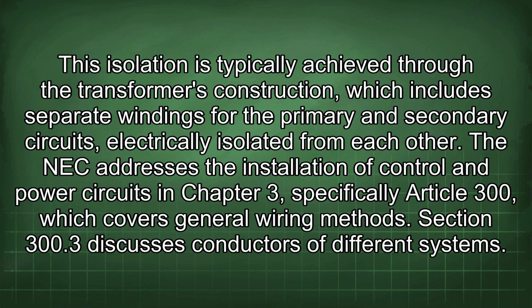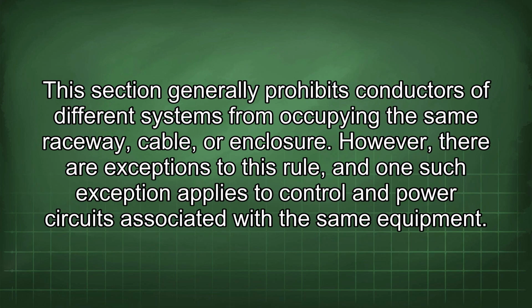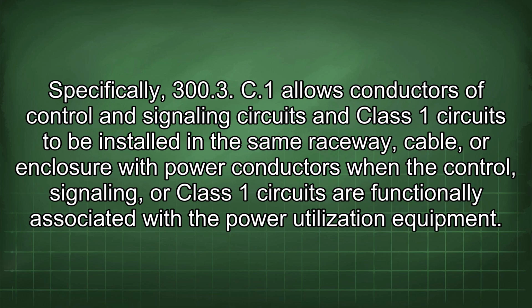Section 300.3 discusses conductors of different systems. This section generally prohibits conductors of different systems from occupying the same raceway, cable, or enclosure. However, there are exceptions to this rule, and one such exception applies to control and power circuits associated with the same equipment. Specifically, 300.3(C)(1) allows conductors of control and signaling circuits and Class 1 circuits to be installed in the same raceway, cable, or enclosure with power conductors when the control, signaling, or Class 1 circuits are functionally associated with the power utilization equipment.